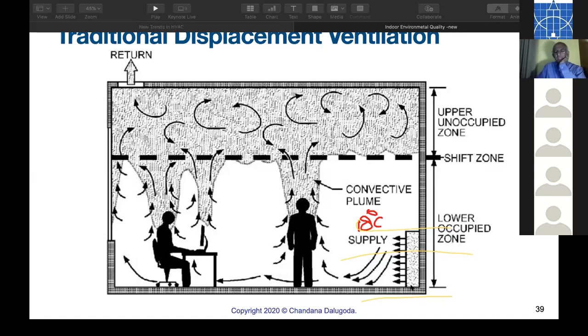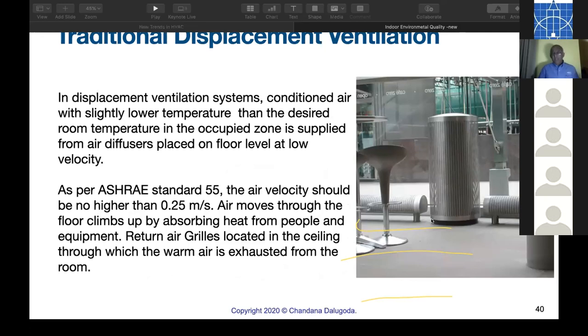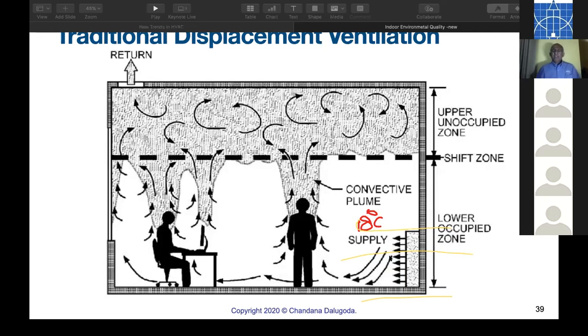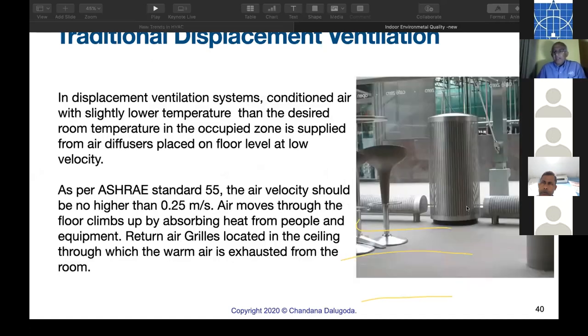Now these grills, diffusers, are specially made, called displacement diffusers. One big advantage is in terms of air quality. The air coming from the outlet is fresh outdoor air with oxygen. In this method, it directly hits the people, so people get oxygen-laden air first. So effectiveness is very high. You can see displacement diffusers.